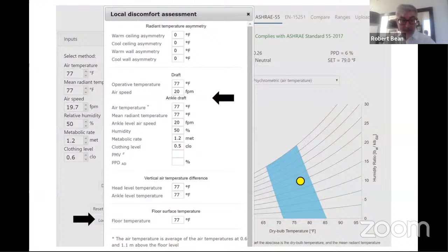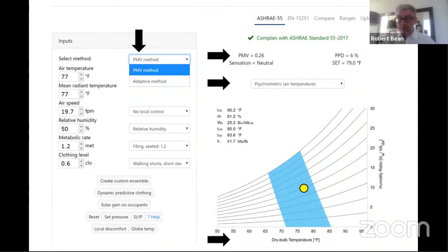So all of these things, when we put them basically in the blender, if you will, the analogy for compliance with ASHRAE 55 is that all of these inputs are like the ingredients of a cake. And when we get all of the ingredients right, the air temperature, the mean radiant temperature, the radiant asymmetry, floors, all of these things, when we get them correct, we will produce a result that is compliance with ASHRAE Standard 55. And that is what we call the predicted mean vote, or the PMV method. And we want to have basically 0 plus or minus 0.5 predicted mean vote, which corresponds to 10% or less predicted percentage dissatisfied. And when we do that, then we will be in compliance with the standard.